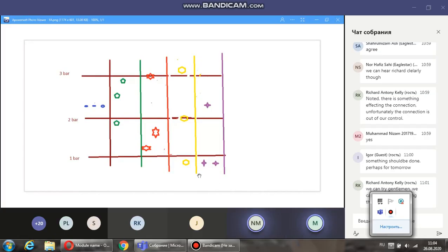Invalidate. Yes, invalidate. So we need to invalidate at least one. In fact, two you can invalidate, no problem. But invalidate one at least. Then this plus this, no matter how much the difference is, we'll take the average. But I would suggest you invalidate both of them because we know the pressure is 2.6 bar. So one good sensor is there, the engine will continue. Then meanwhile, try to replace these two sensors.